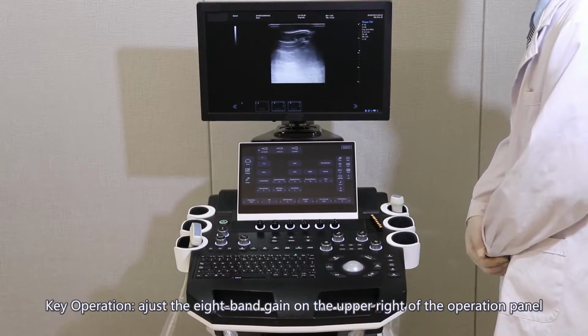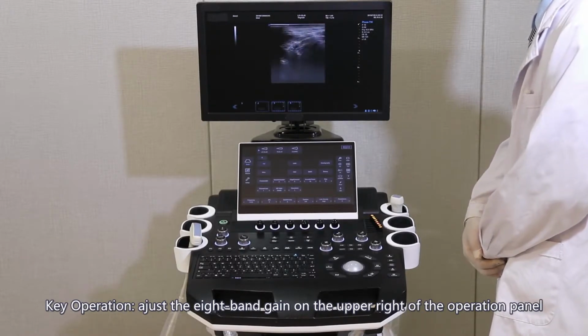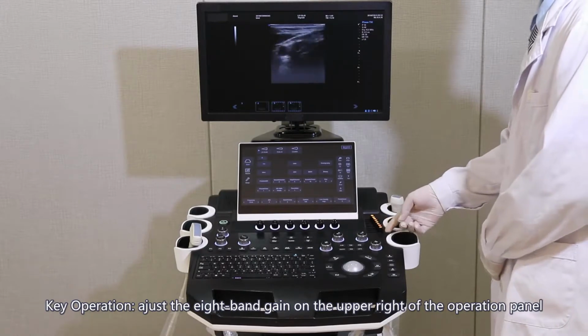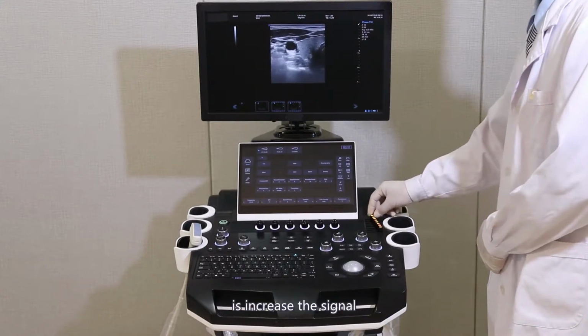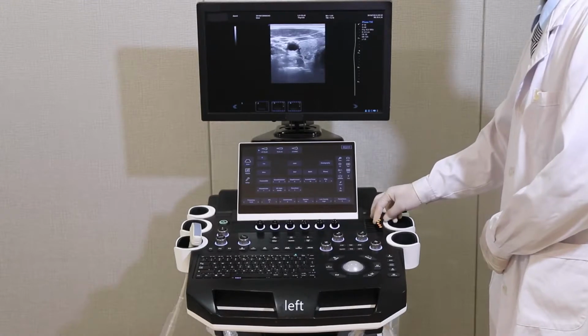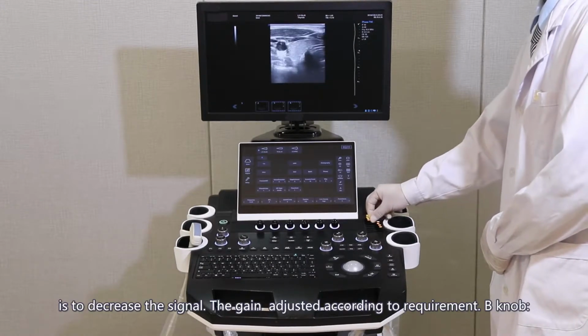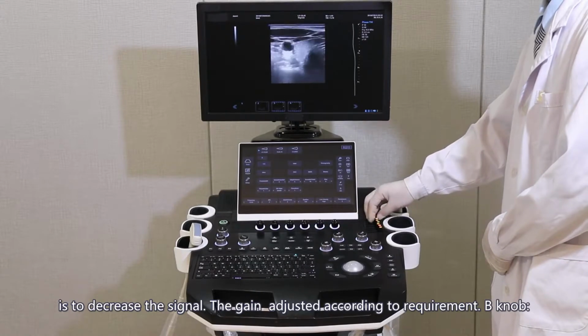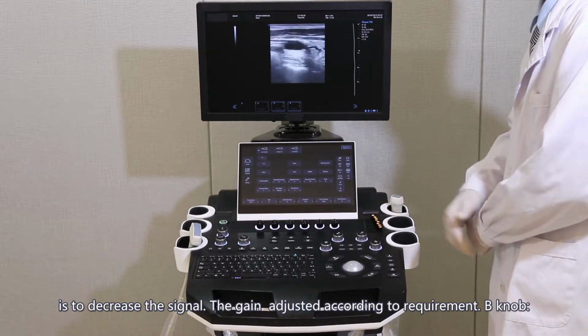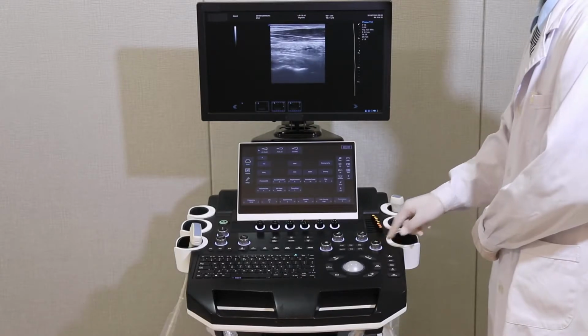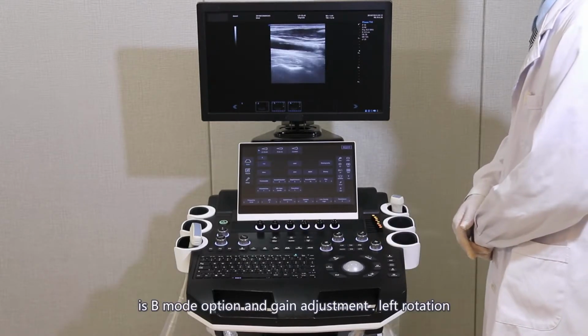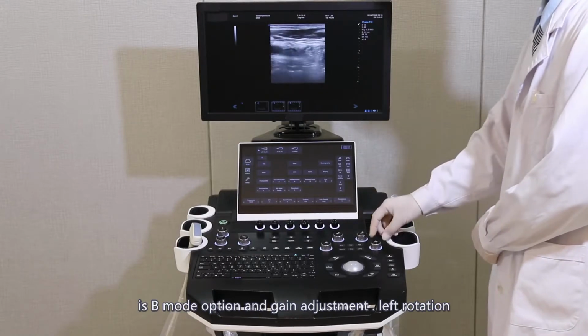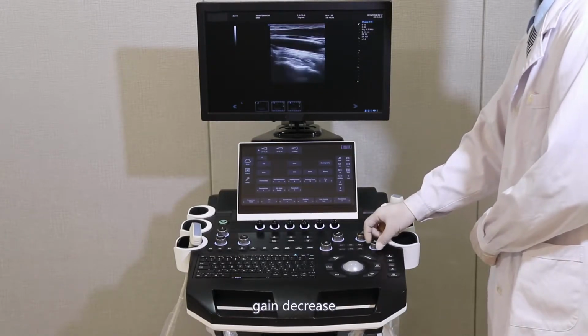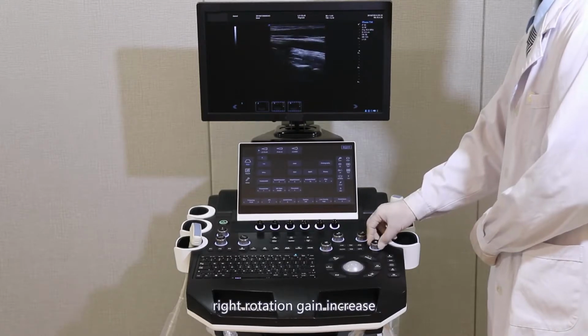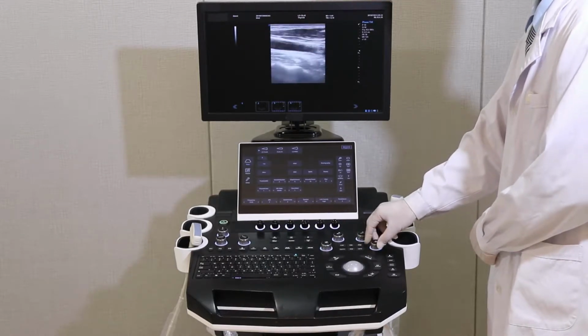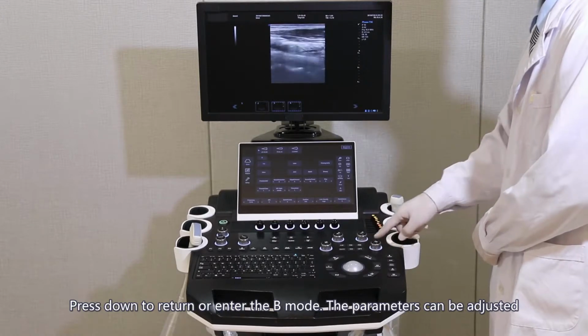Key operation. Adjust the 8-band gain on the upper right of the operation panel. Right is increase the signal. Left is to decrease the signal. The gain adjusted according to requirement. B knob. It's a B mode option and gain adjustment. Left rotation, gain decrease. Right rotation, gain increase. Press down to return or enter the B mode.